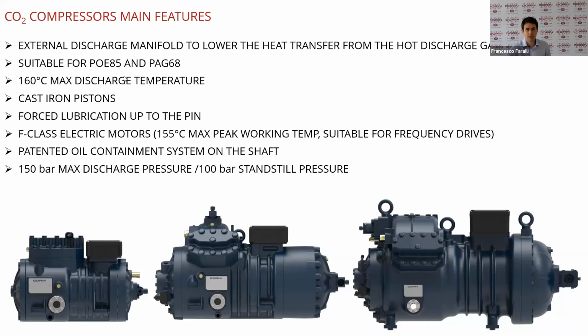So the most important aspect for sure is the external discharge manifold that lowers the heat transfer from the hot gas discharge flow to the oil. This is for sure also one of the most recognizable aspects of our transcritical CO2 compressors. These compressors, depending on the application, can work with the POE 85 or PAG 68. The maximum discharge temperature sensor is set at 160 degrees Celsius.